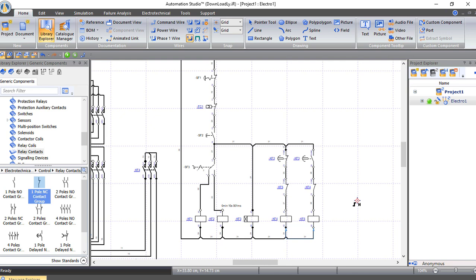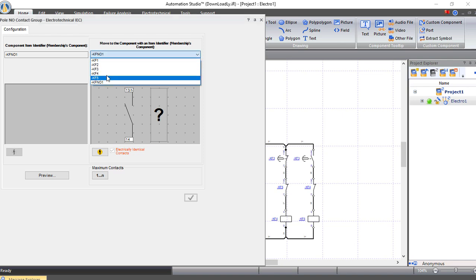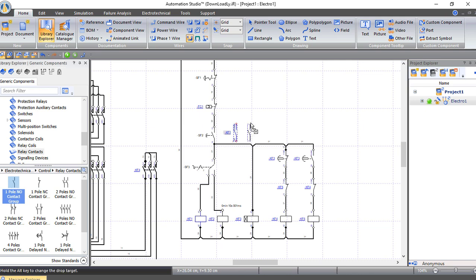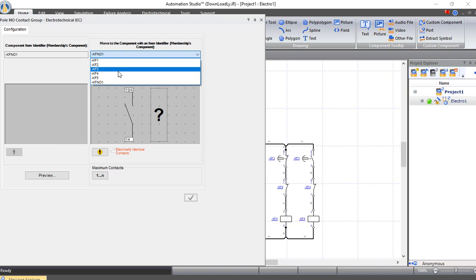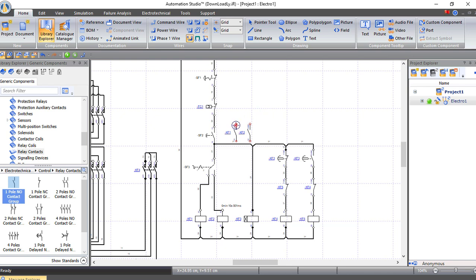Now the start is working as jogging — we need a latched contact from the main contactor, which could be K1 or K2. We will bring two normally open contacts: one from K1 set to KF1 and one from K2 set to KF2, to make a holding contact. Now let's connect them in parallel with our start push button.